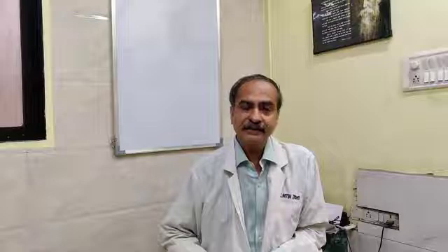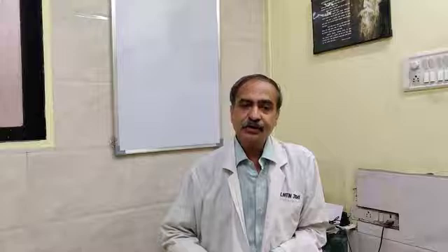Then comes the patient point, that is, one has to see that there is no contact of the patient with the metal part of the operating table, and there are no damp pathways, that is bridges, because of dampness of the clothes of the patient or between the patient and the operating table.